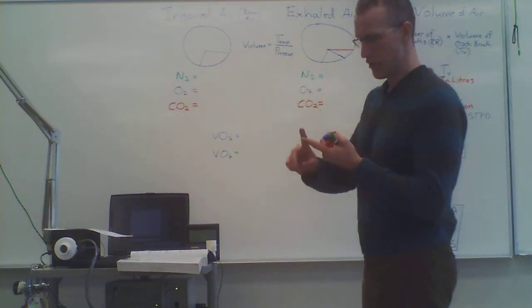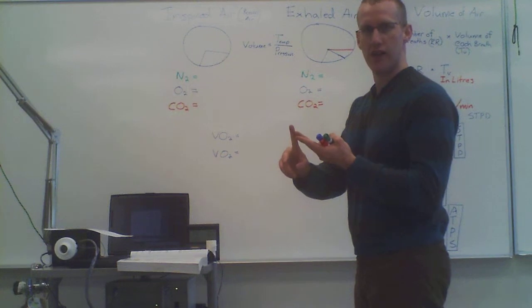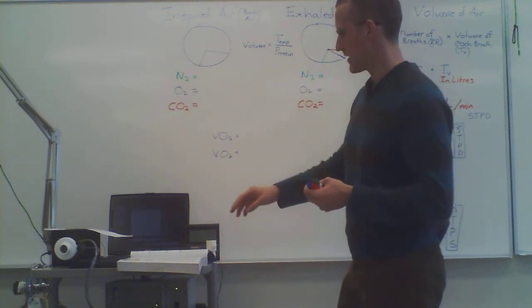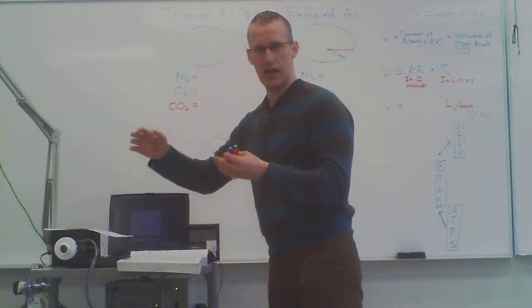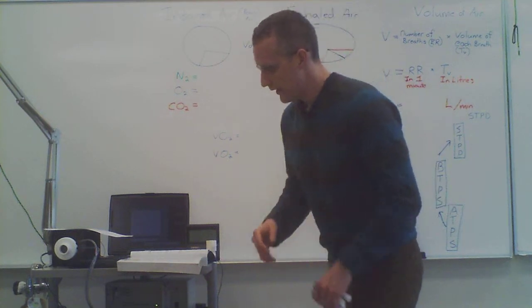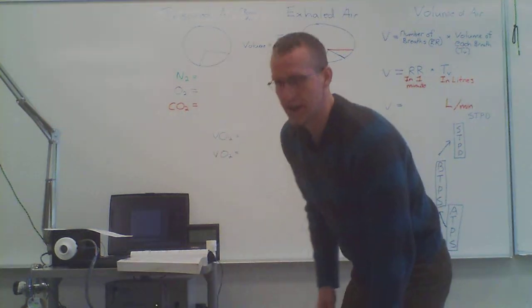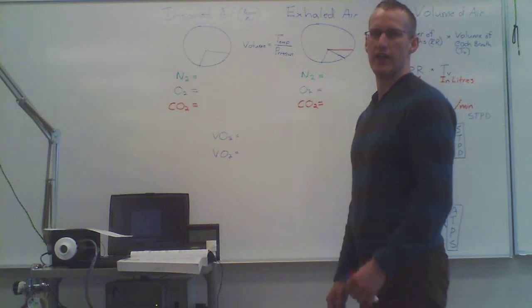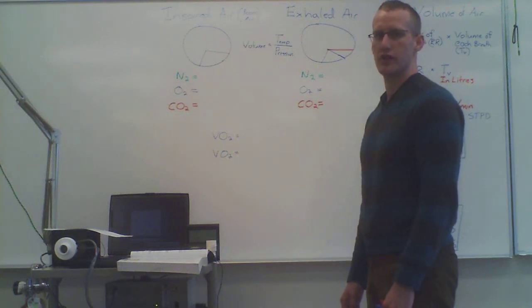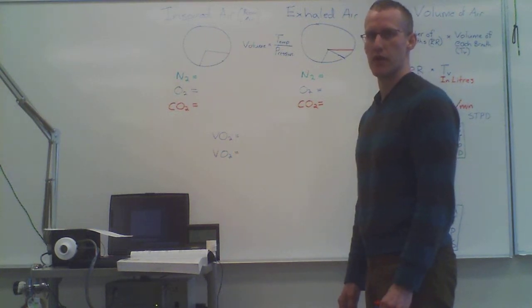Secondly, it measures oxygen and carbon dioxide in that air. So it has a little sampling line at the back. It takes a sample of the air. And then the sensors inside the cart can measure what percentage of that air is oxygen and what percentage is carbon dioxide.